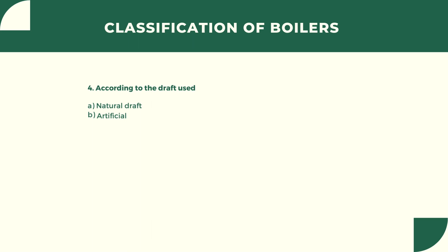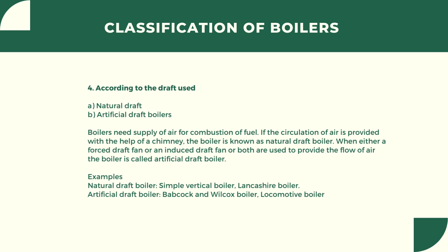According to draft, boilers can be classified into two categories: natural draft and artificial draft boiler. First, we see what is a natural draft boiler. A boiler needs a supply of air for combustion of fuel. If the circulation of air is provided with the help of a chimney, then that boiler is called a natural draft boiler. When either a forced draft fan or an induced draft fan or both are used to provide the flow of air, then that boiler is called an artificial draft boiler. Natural draft boiler examples are simple vertical boiler and Lancashire boiler, and artificial draft boiler examples are Babcock-Wilcox boiler and locomotive boiler.